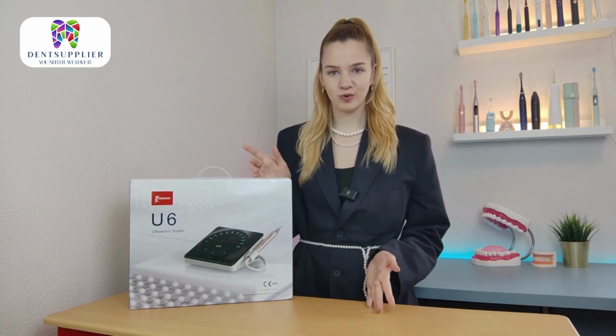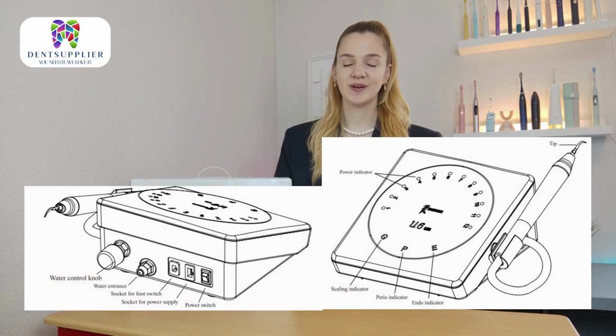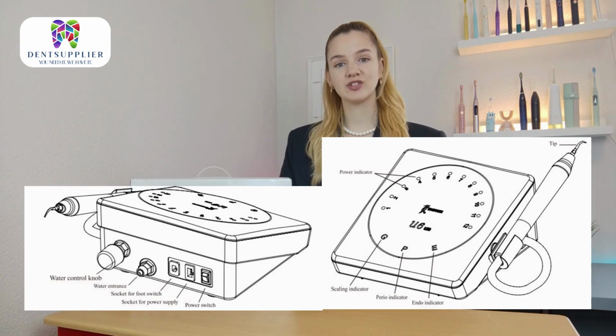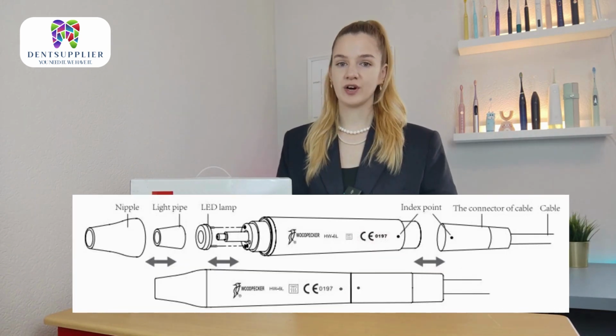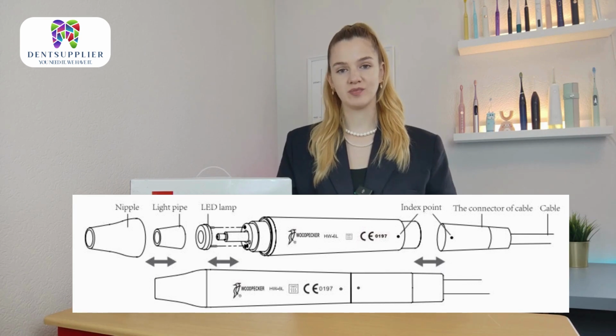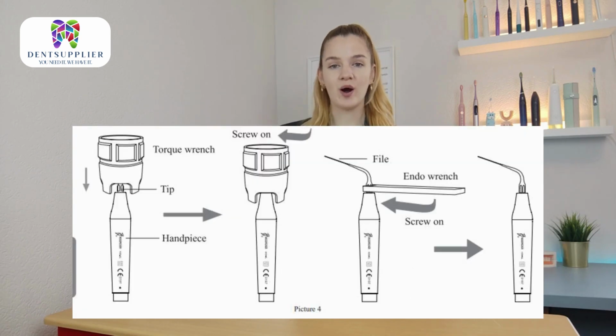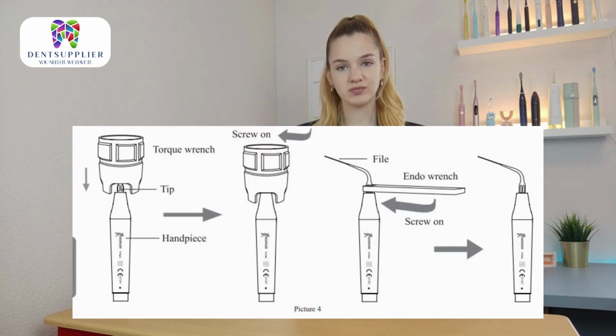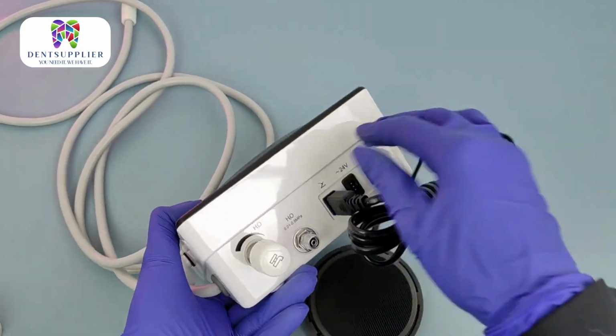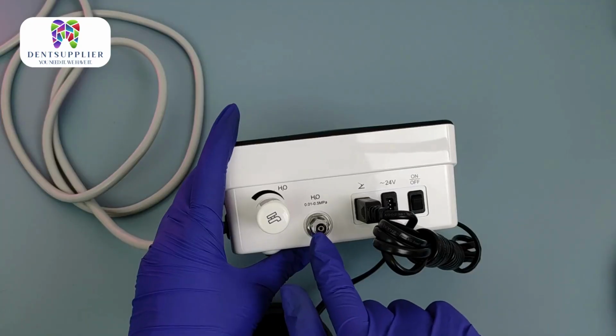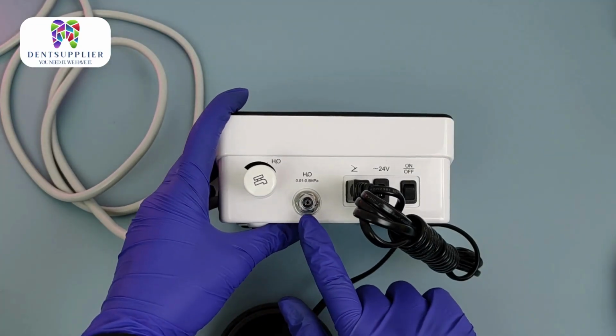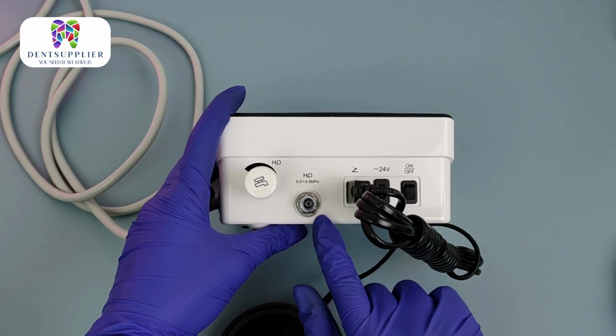And now let's see how we can install this device and prepare it for work. Here you can see a quick explanation for each button and connection on the device. Here is short instruction how to install the handpiece. And here is an explanation on how to add a tip using a wrench. Insert the plug of the foot switch to the socket. Connect one end of the water pipe to the water entrance and the other end to the clean water source.